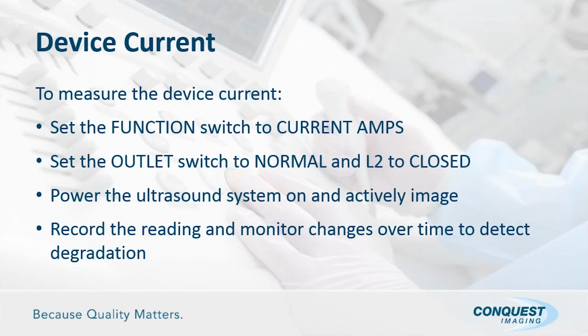To measure device current on an ESA601, set the function switch to current amps, set the outlet switch to normal, and then the L2, which is considered the neutral wire, closed. Power the ultrasound system on and actively image again, and record the reading and monitor changes over time to detect degradation. Two things, again: make sure you're checking all imaging modes when you say actively imaging. Also, when it says monitor changes over time, it's not enough to just write this down. Say it's running at 5 amps today, and 6 months later we do another electrical safety check and it's running at 7 amps.